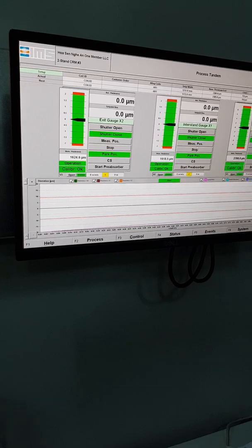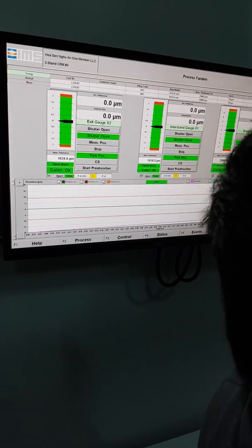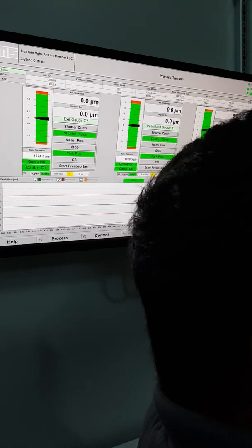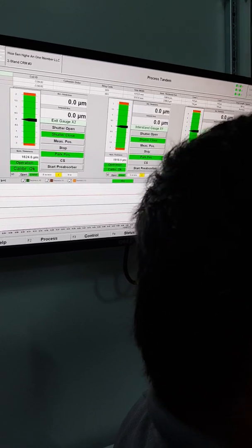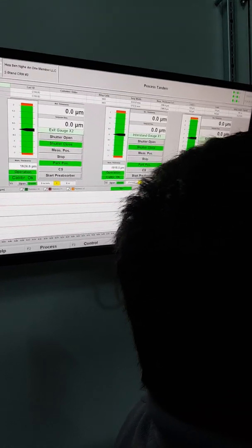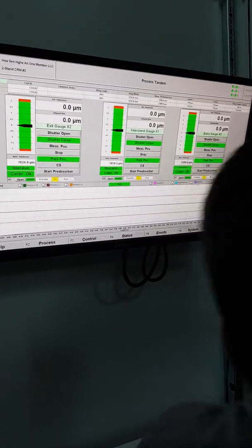Okay. One thing, if the bus is not running, you will see only the white light, no green light there. Okay. If the bus is not running, suppose you came in the morning and you see that only the white light is glowing, that means the bus is not running in the system. Okay. How will you check?